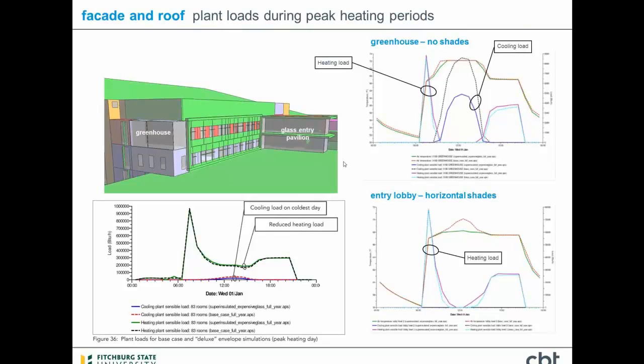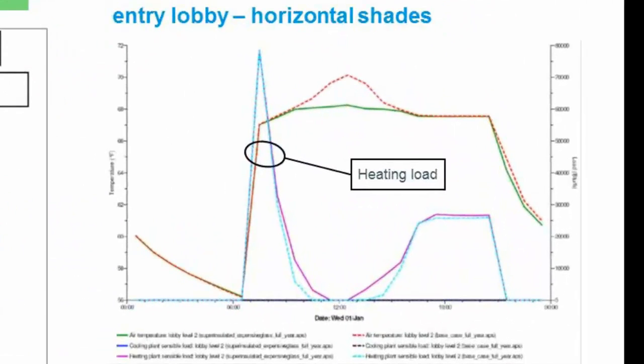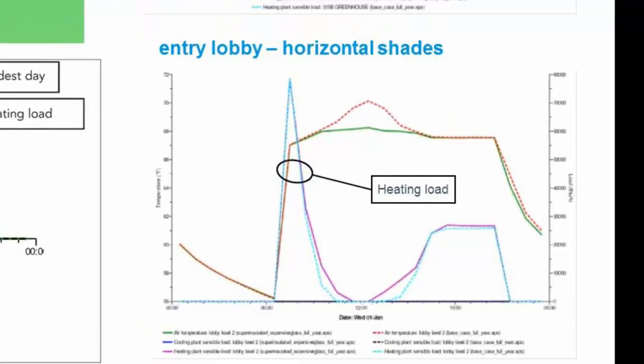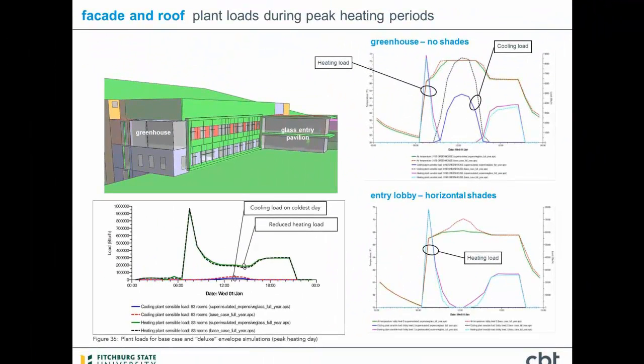So I was curious and looked back at our entry pavilion that we discussed before, and if you look at the same space, you have a similar pattern where the heating load in the morning drops off, but because of those overhangs, you never get into a situation where there was a call for any cooling during that winter day. So in addition to that, we were able to identify the greenhouse as a location where we wanted to add some operable lights to the windows so that we could avoid having to cool that in the winter months.